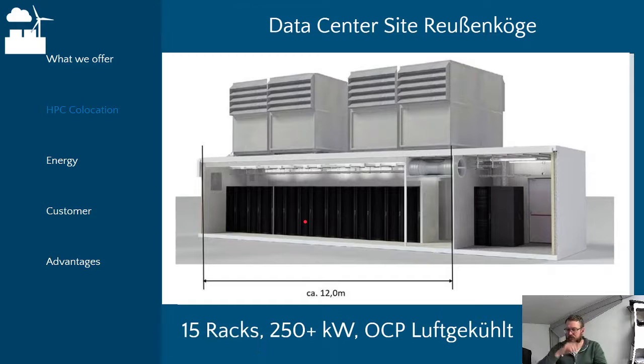This is the OCP module and the cooling equipment I mentioned: an indirect free cooling system. Basically, air moves through an air-to-air heat exchanger, with outside air coming in cold and going out hot. The cold air created is brought in front of the servers, moves through them creating warm air, which is sucked in on the back of the cooling units, and the cycle starts all over again.